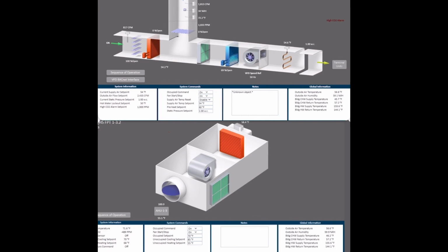Okay, so what I was saying about the VAV box is you don't need the blower running for cooling at all times in some VAV boxes and some different types of systems. And for heating, you can also have electric heating instead of boilers or hot water. But anyways, let's talk about the air handler unit, so you know where you're getting the cooling from.